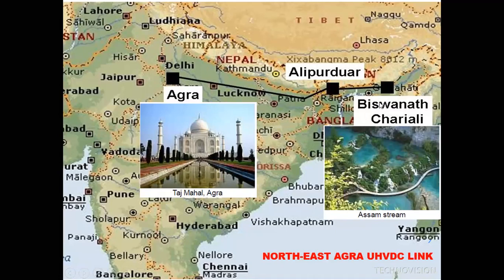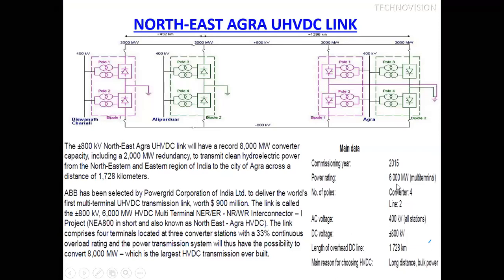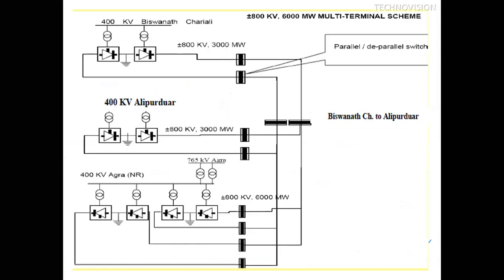So this is a very special kind of link in the world, and it has a transmission capability of 6,000 megawatt. There are 2 bipoles, and each bipole has a capacity of 3,000 megawatt. The distance from Assam to Agra is 1,728 kilometers. We generally prefer HVDC transmission when the distance increases beyond 700 to 800 kilometers. That is known as the break-even distance. So for bulk power transmission, we have adopted this multi-terminal HVDC link. These are the rectifier stations, and this is the inverter station at Agra.